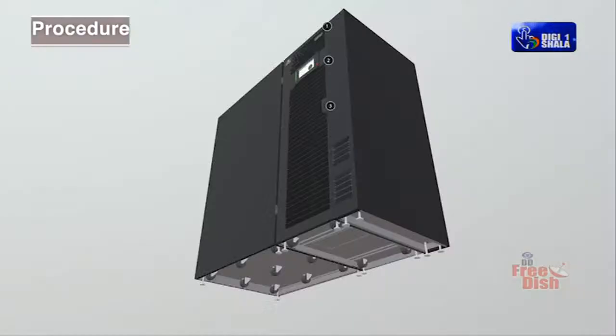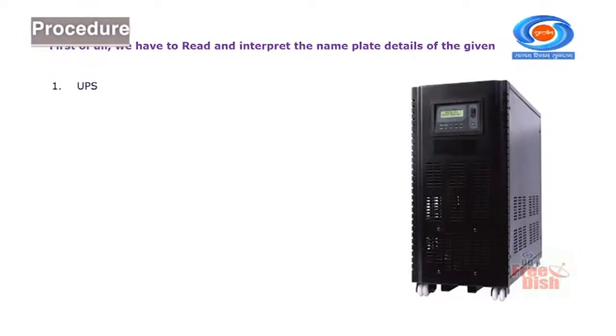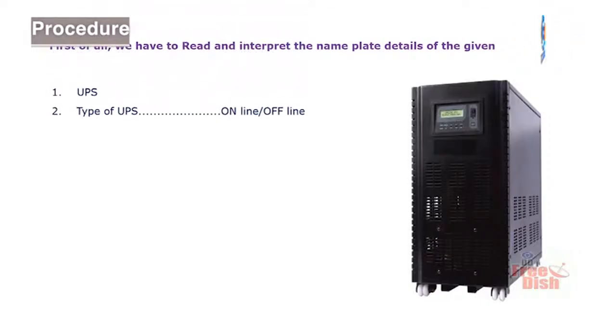In this exercise, our third task is to test the UPS, identify the faults and rectify them. First of all, we have to read and interpret the nameplate details of the given UPS: type of UPS, online or offline, model, power rating in VA, changeover time, battery rating, and backup time.